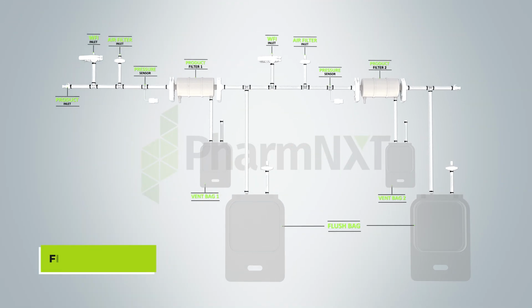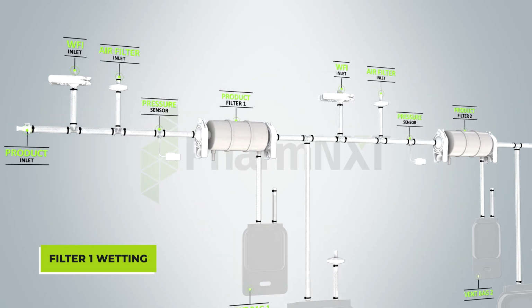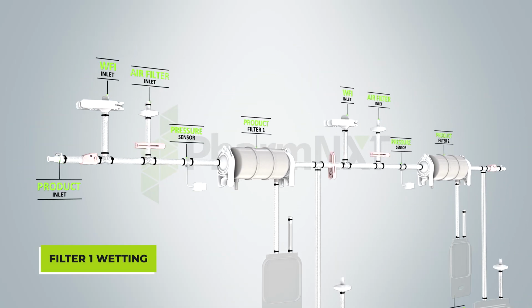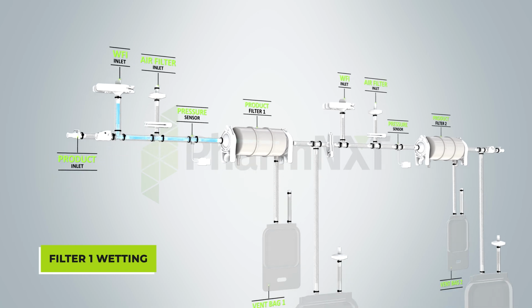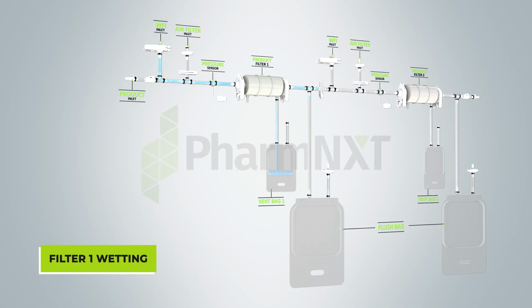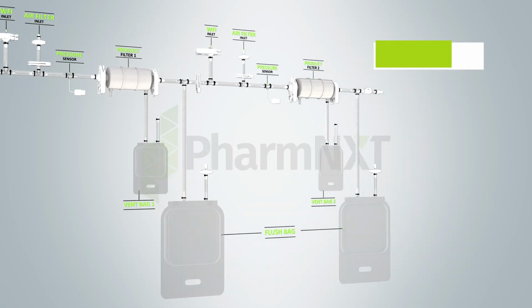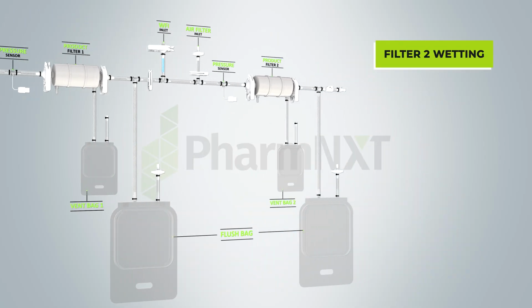Our first step is filter wetting. Proper wetting is crucial for accurate integrity testing, as it ensures the filter's pores are fully saturated. This step creates consistent conditions similar to actual filtration, using a compatible wetting agent like water for injection, WFI, or isopropanol for hydrophobic filters. To achieve complete saturation, the filter is vented to eliminate air pockets.